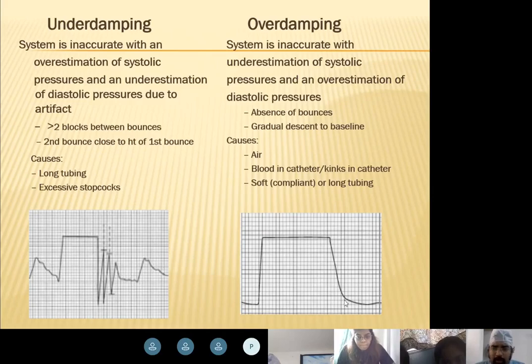That means there is some problem in your waveform, and that problem could be air bubbles, catheter kinking, blood in the line, or your tubing is not proper. Usually it is either a clot, an air bubble, or a kink. These are the problems that you will probably get if you get an overdamped waveform. So in this case, what do you do? You open up the catheter, check whether there is any kink, and flush the device with a fast flush.